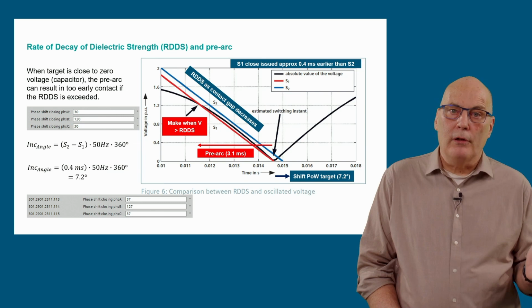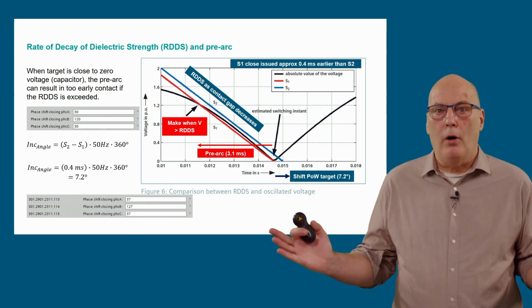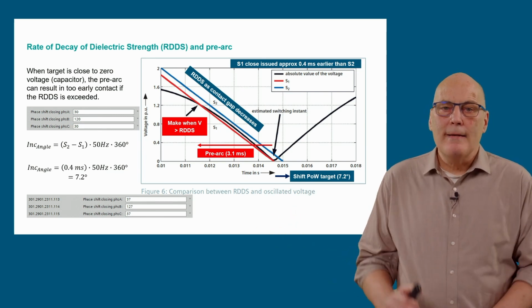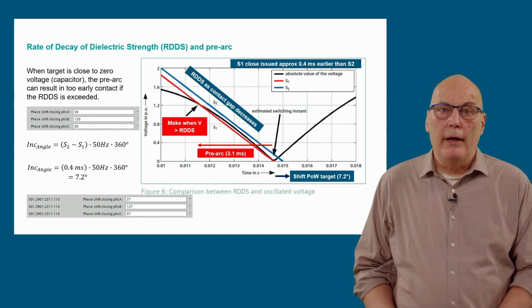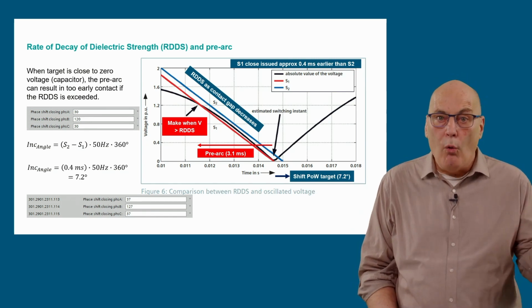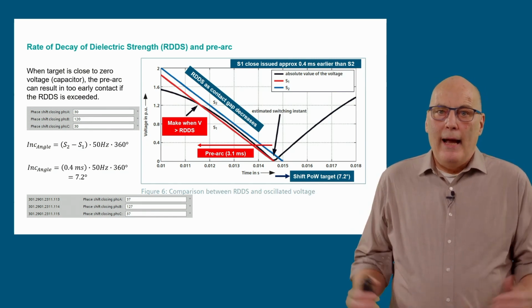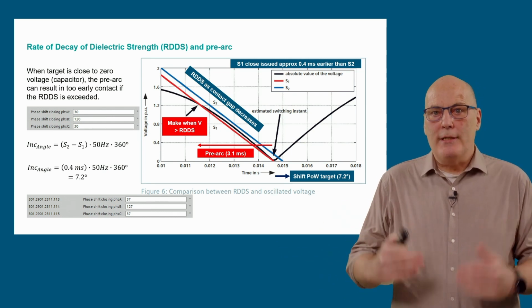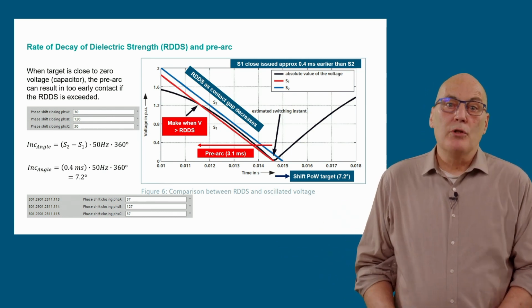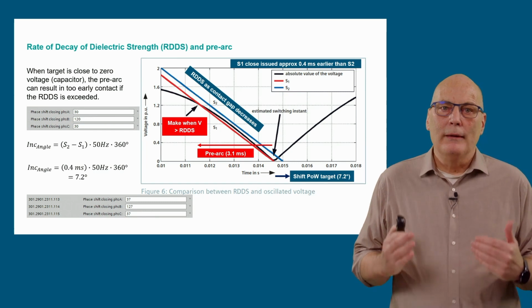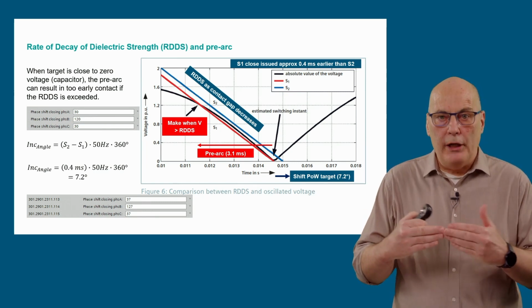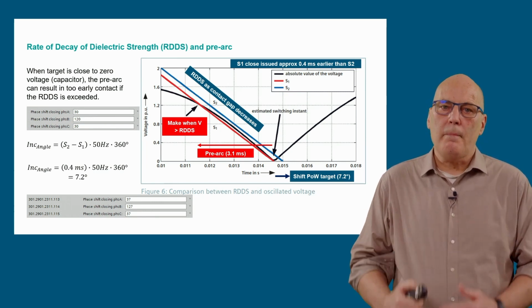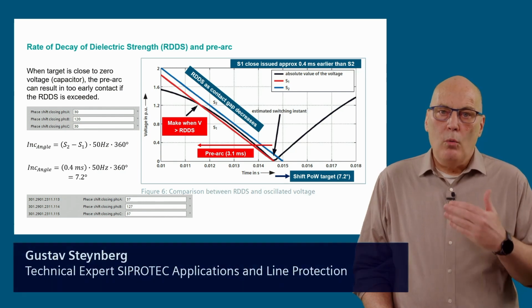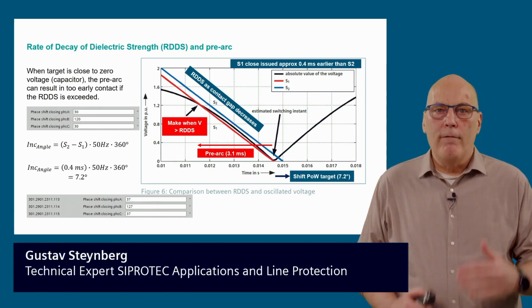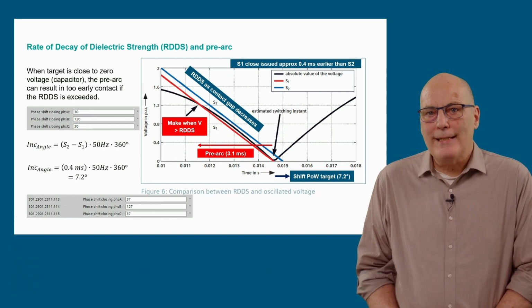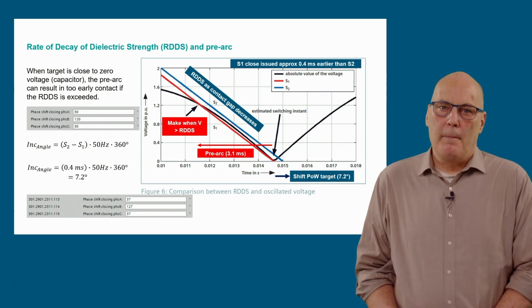On the vertical axis, voltage is the indicated value. At the start of the close process, the contacts are far apart and the RDDS is very large. As shown by the S1 and S2 curves, they are off the scale. As the separation of the contacts decreases, the RDDS voltage values decrease until it is zero when the separation is also zero. Pre-arc will occur when voltage across the contacts exceeds the RDDS curves.